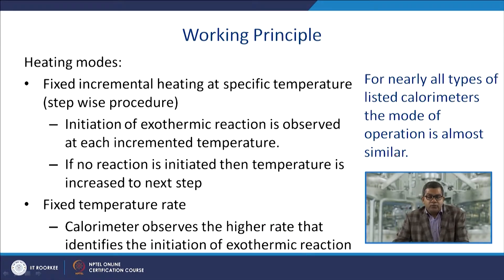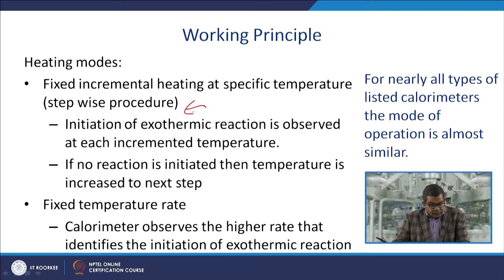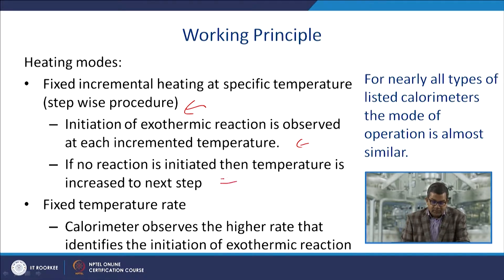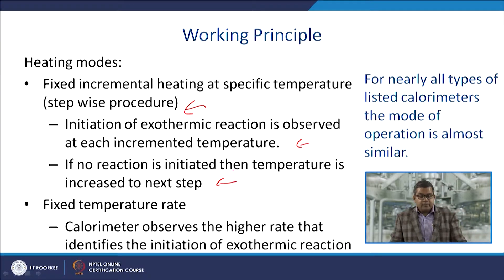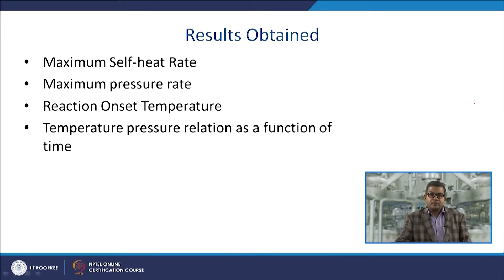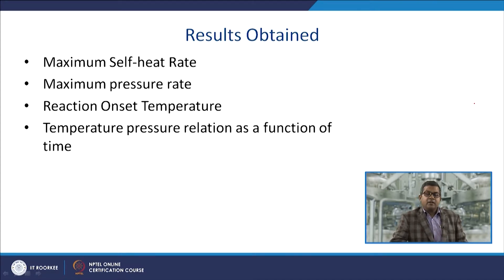The working principles of these calorimeters include a heating mode with fixed incremental temperature steps, where initiation of exothermic reaction is observed at each increment. If no reaction is initiated, the temperature is increased to the next step. Alternatively, a fixed temperature rate mode is used where the calorimeter identifies the initiation of exothermic reactions. Results include maximum self-heat rate, maximum pressure rate, reaction onset temperature, and the temperature-pressure relationship as a function of time.